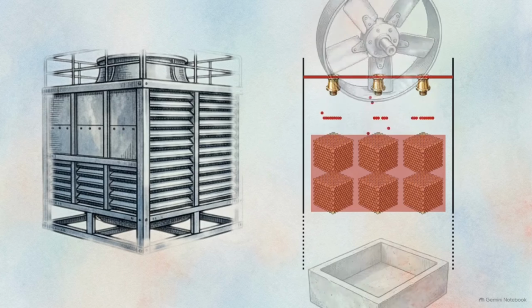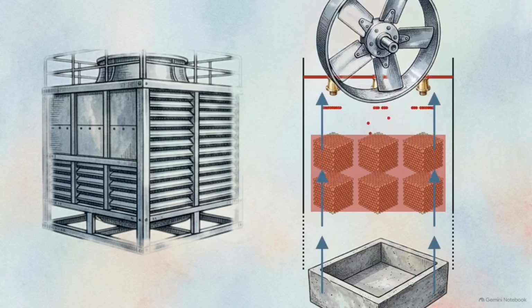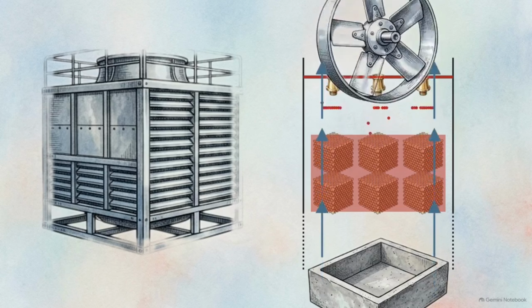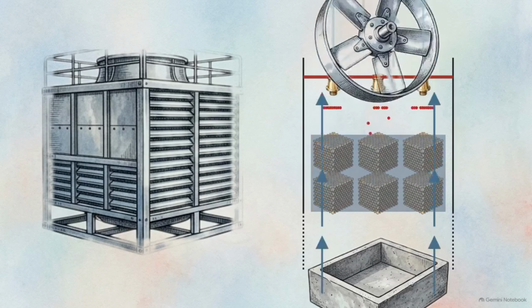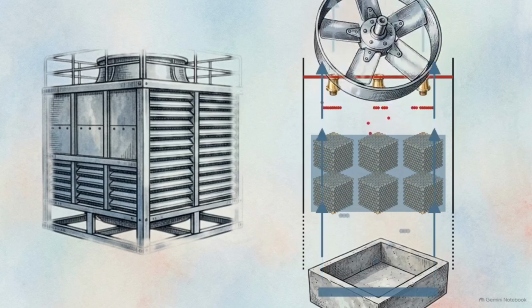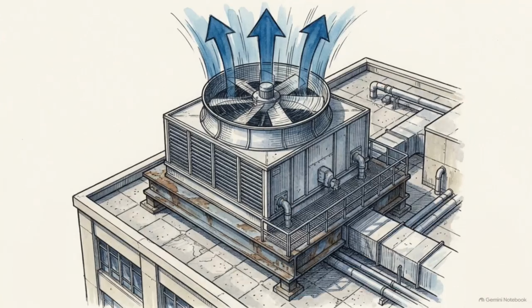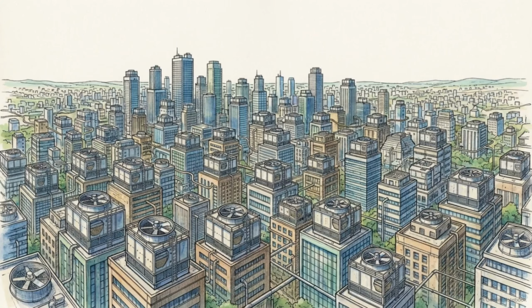To maintain the evaporation rate, the system requires continuous forced airflow. A massive mechanical fan at the top of the structure constantly draws fresh air upward, directly through the falling water film. Because the fan pulls rather than pushes the air through the unit, this specific configuration is known as an induced draft tower. It is the absolute standard across commercial HVAC plants.